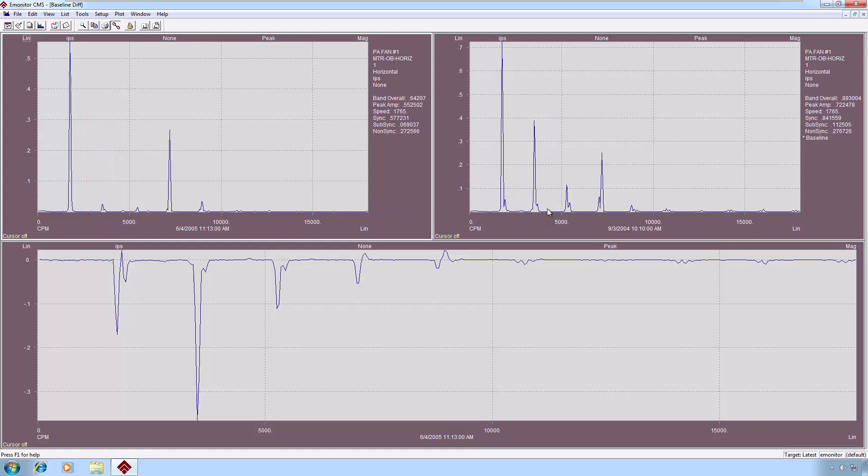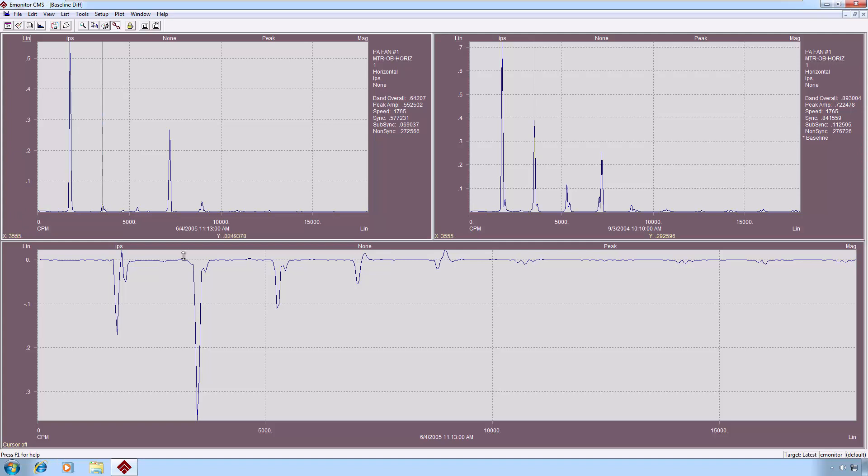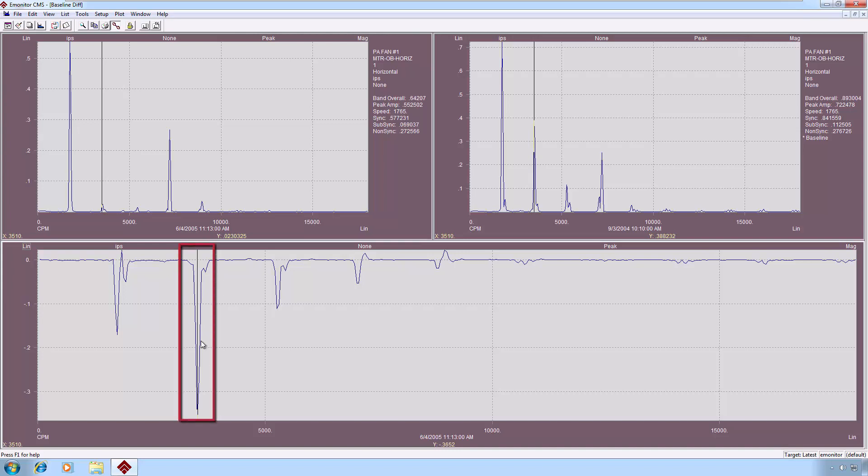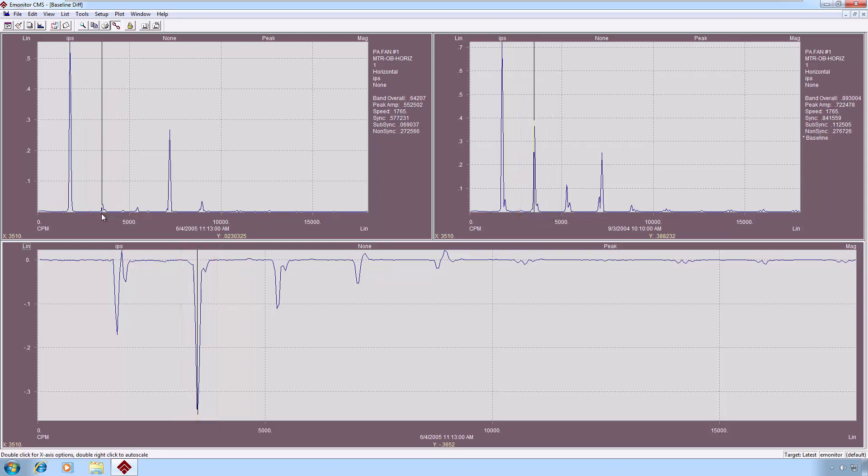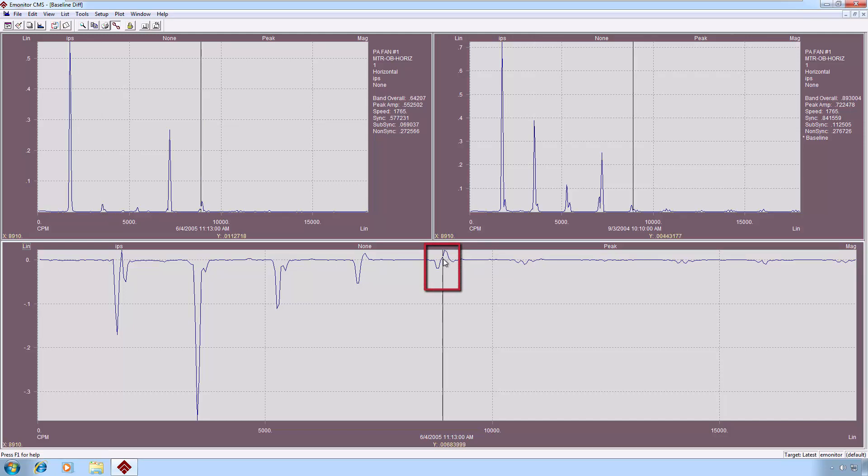So I actually have a negative amplitude because my peak has gone down. Now one place where that is not true is on this particular peak right here. So we could click on this peak in the plot and position it with the arrow keys if we need to, and it will put the cursor on the spot of both the baseline and the current cursored spectrum.